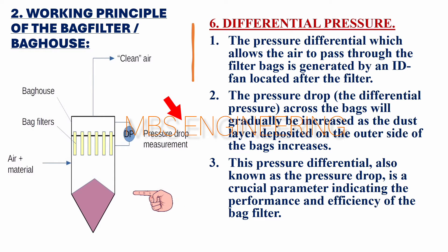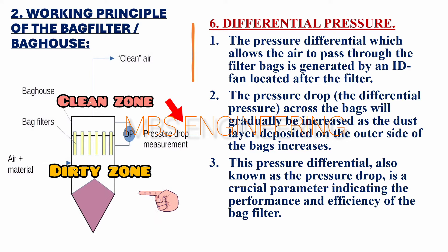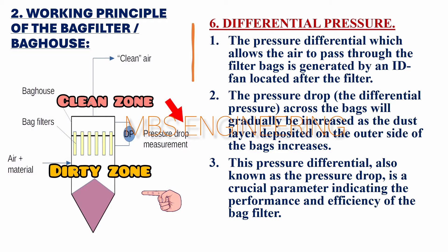Please refer to the bag house system differential pressure transmitter, which is used to show the pressure drop between the clean gas zone side and the dirty gas zone side. The pressure drop across the bags gradually increases as the dust layer on the outer side of the bags increases.